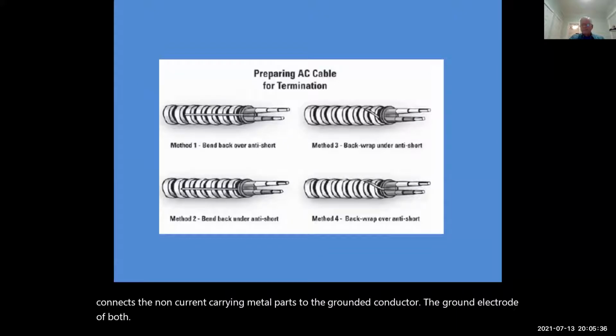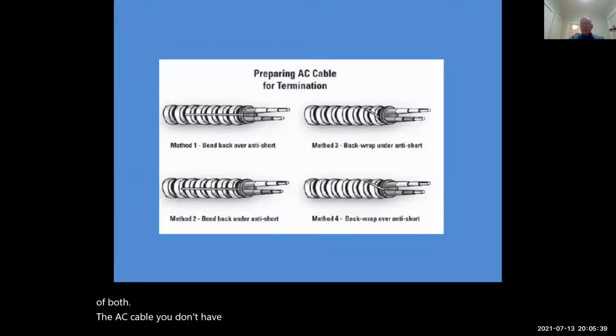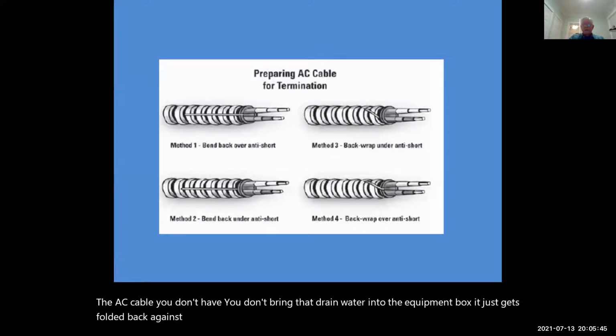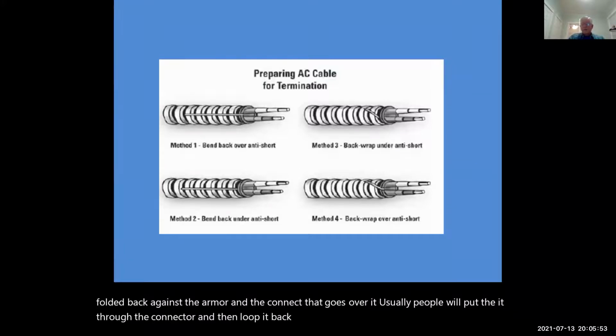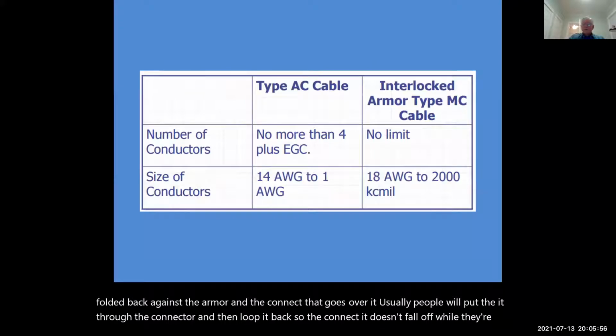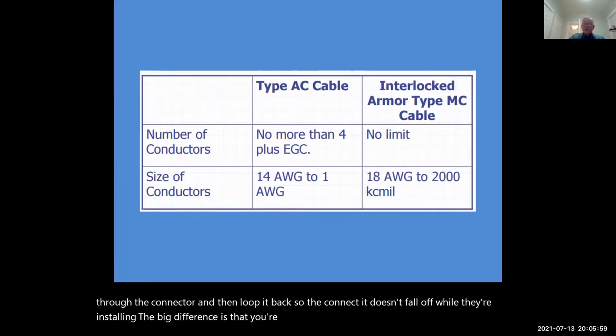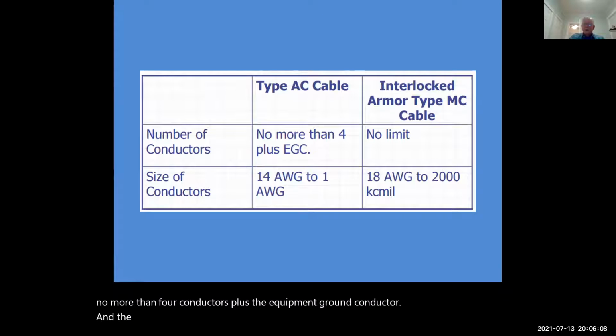With the AC cable, you don't bring that drain wire into the equipment box. It just gets folded back against the armor, and the connector goes over it. Usually people will put it through the connector and then loop it back so the connector doesn't fall off while they're installing it. The big difference is the number of conductors: there's a limit in AC cable, no more than 4 conductors plus the equipment ground conductor, and limits on the sizes. MC cable can have as many conductors as you can make it big enough to fit, and from small to extremely large in wire size.